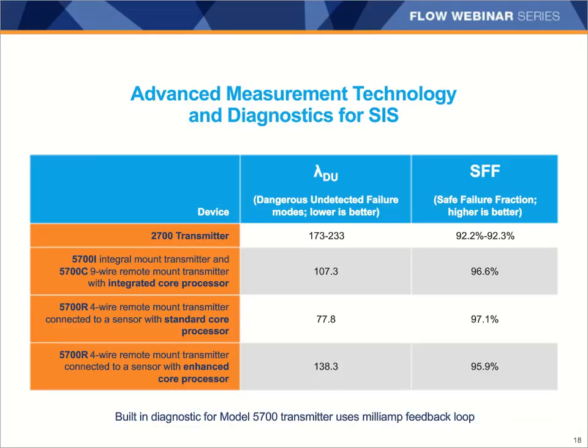So let's take a look at some of the safety scores for the Micro Motion Coriolis meters. As you can see, all of the SFFs are in the 90+% range. And just for reference, some other Coriolis meters may be in the high 80s or the very low 90s from numbers that we've seen. The Model 2700 has good SFF values, but the Model 5700 is even better. It's best in class, in fact, with SFF values in the mid to high 90% range. So you can see here it's like in the 96 to 97% range.